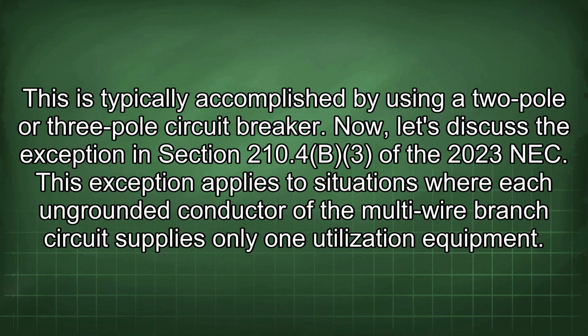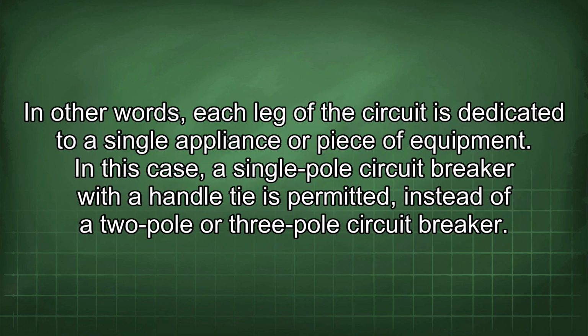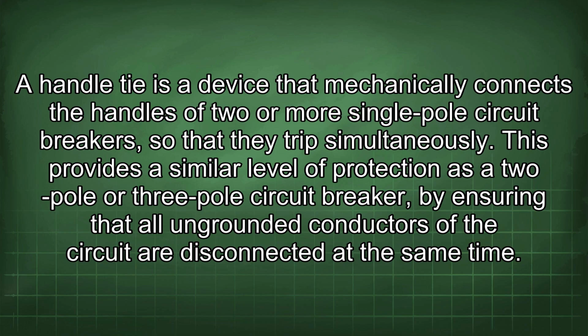Now, let's discuss the exception in section 210.4(B)(3) of the 2023 NEC. This exception applies to situations where each ungrounded conductor of the multi-wire branch circuit supplies only one utilization equipment. In other words, each leg of the circuit is dedicated to a single appliance or piece of equipment. In this case, a single-pole circuit breaker with a handle tie is permitted, instead of a 2-pole or 3-pole circuit breaker. A handle tie is a device that mechanically connects the handles of 2 or more single-pole circuit breakers so that they trip simultaneously. This provides a similar level of protection as a 2-pole or 3-pole circuit breaker by ensuring that all ungrounded conductors of the circuit are disconnected at the same time.